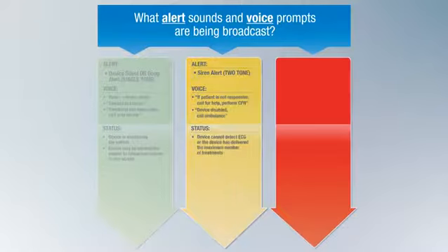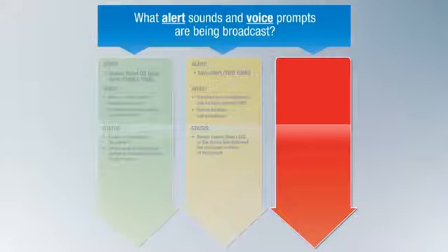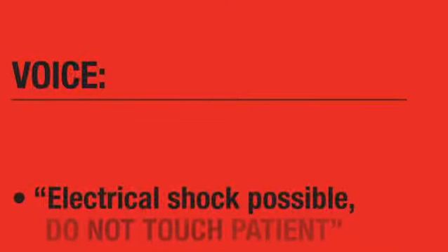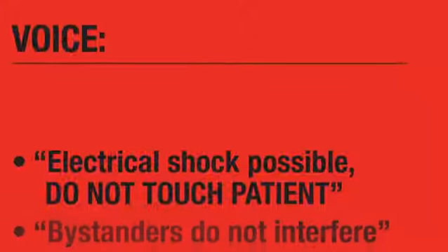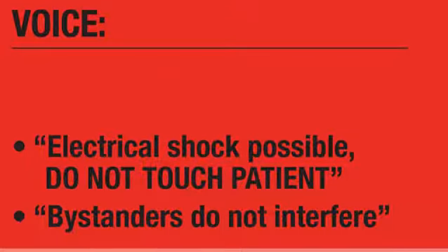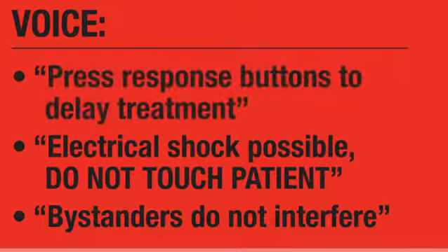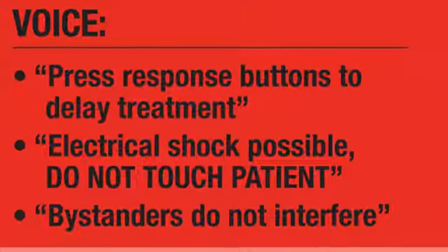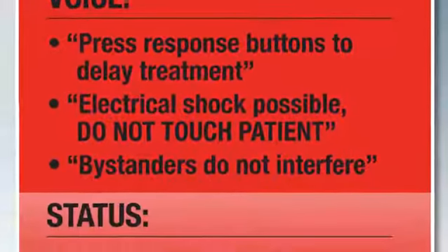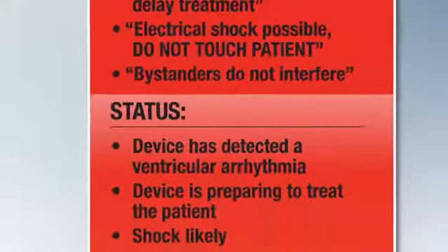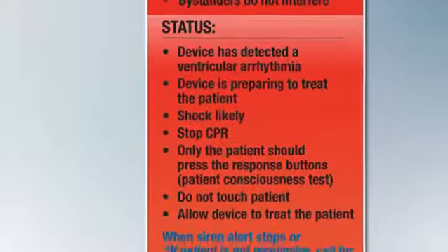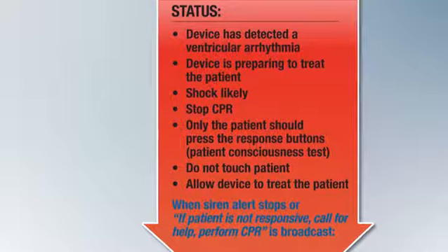If the LifeVest has detected a ventricular arrhythmia and is preparing to treat the patient, the two-tone siren alerts will be accompanied by this voice prompt. "Electrical shock possible. Do not touch patient. Bystanders, do not interfere." When the LifeVest is in this mode, an electrical shock will be delivered between 25 and 60 seconds after the treatment sequence begins, depending on the type and rate of the arrhythmia and whether the patient presses the response buttons.